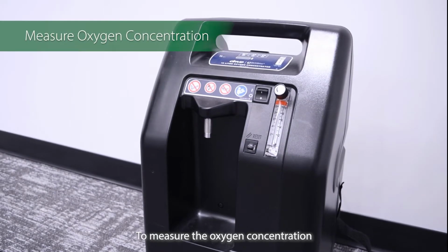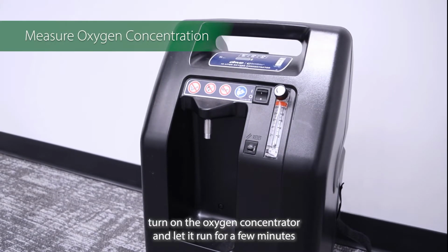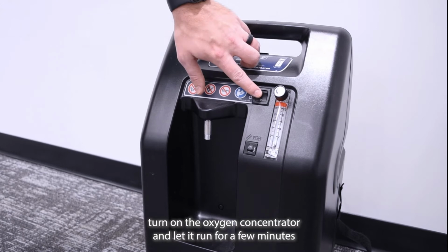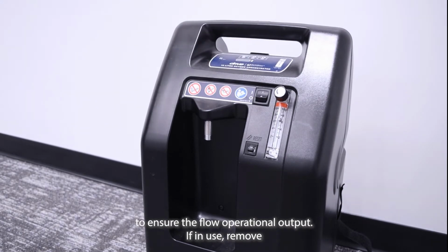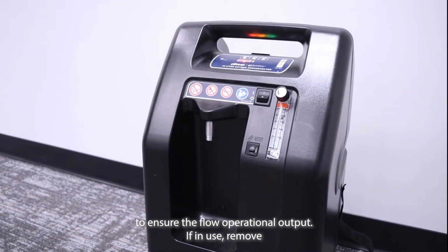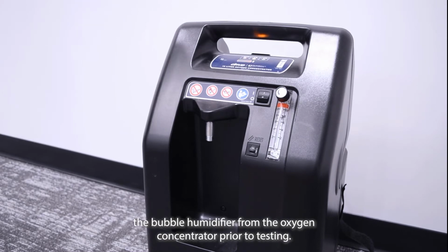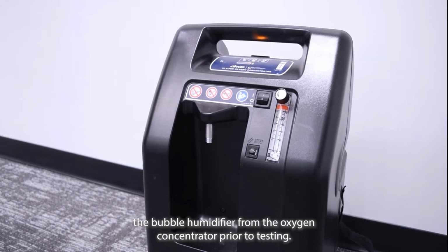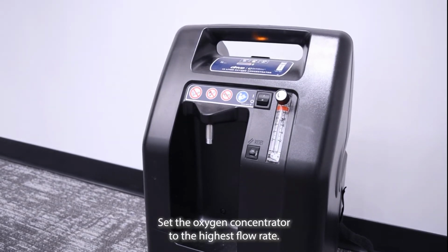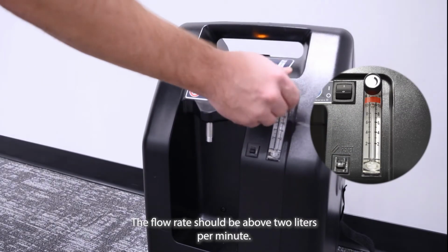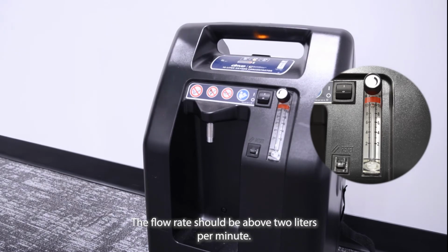To measure the oxygen concentration, turn on the oxygen concentrator and let it run for a few minutes to ensure the flow operational output. If in use, remove the bubble humidifier from the oxygen concentrator prior to testing. Set the oxygen concentrator to the highest flow rate. The flow rate should be above 2 liters per minute.